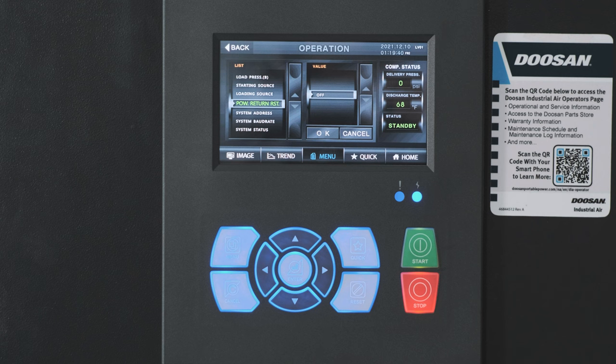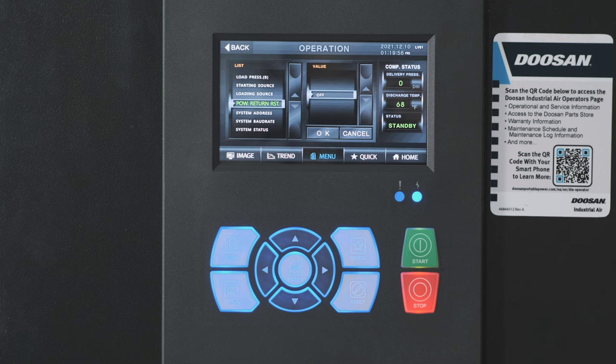Power Return Restart, or PRR. With the PRR on, the compressor will return to the operational state it was in prior to losing power. So if the compressor was in standby and power is lost, when power is restored, the compressor will return to the standby state.